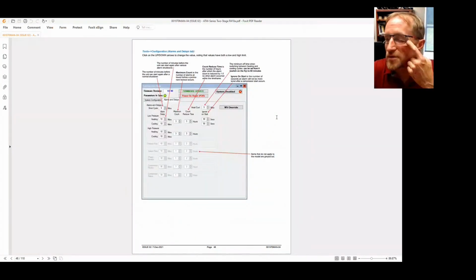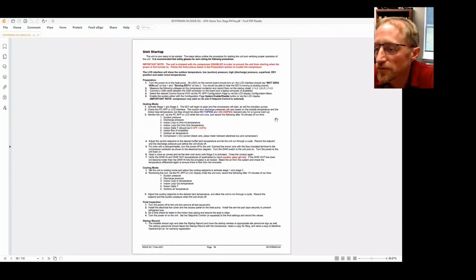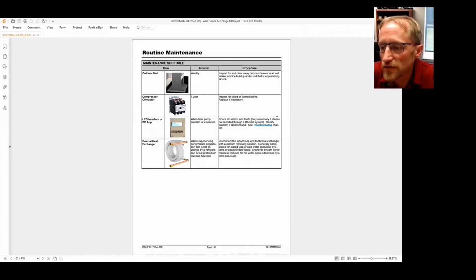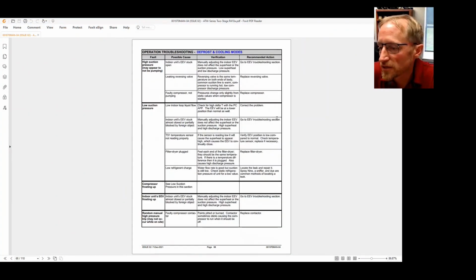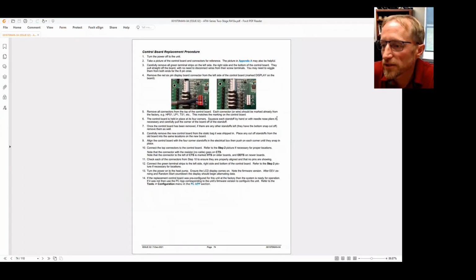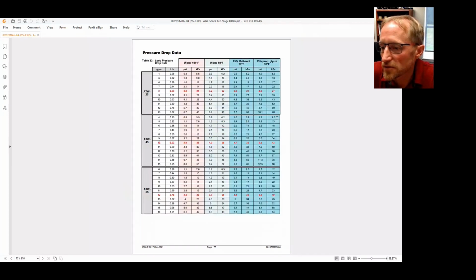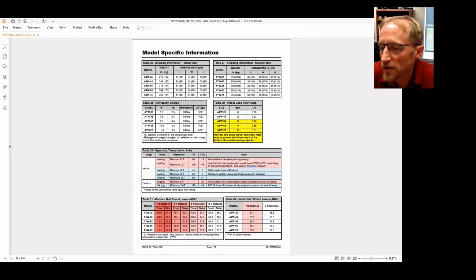Well, the specifications of the heat pump are for coldest leaving water temperature, and there's a min-max temperature table toward the end of the manual here. Let me just go to it. Operating temperature limits. So for cooling, we're saying that the minimum leaving water temperature is 41. So a reasonable minimum set point is probably 42, something like that.